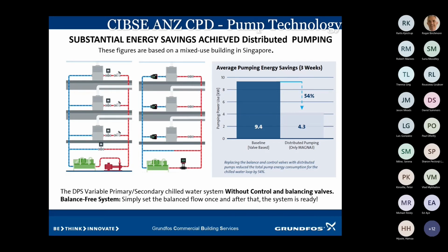You'll notice between the two of them again, it's gone from a primary to a primary and tertiary pump. The first one on the left-hand side is one pump only, a primary pump. It has to feed through every piece of that pipework in every part of that unit. Whereas now, on the second one here on the right, you've got the small primary pump. All it's doing is feeding water through that loop, through that chiller, through that little bottom end loop. The little pumps are drawing off that, so each one of those is individually sized. This, on the right-hand side, the blue box here, was a job done at the Ngee Ann University in Singapore, and they had nearly 55% energy savings. Then they had to change their primary pump because it was oversized.